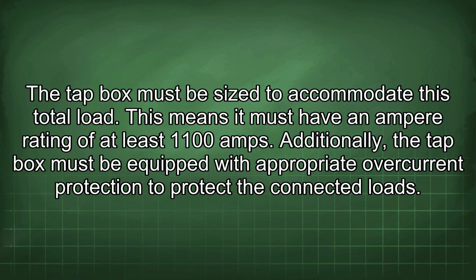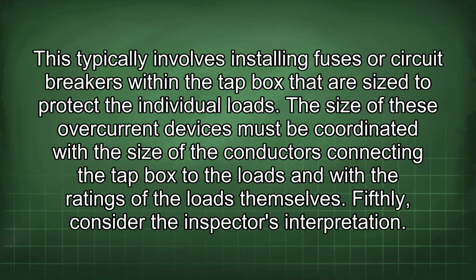Additionally, the tap box must be equipped with appropriate overcurrent protection to protect the connected loads. This typically involves installing fuses or circuit breakers within the tap box that are sized to protect the individual loads. The size of these overcurrent devices must be coordinated with the size of the conductors connecting the tap box to the loads and with the ratings of the loads themselves.